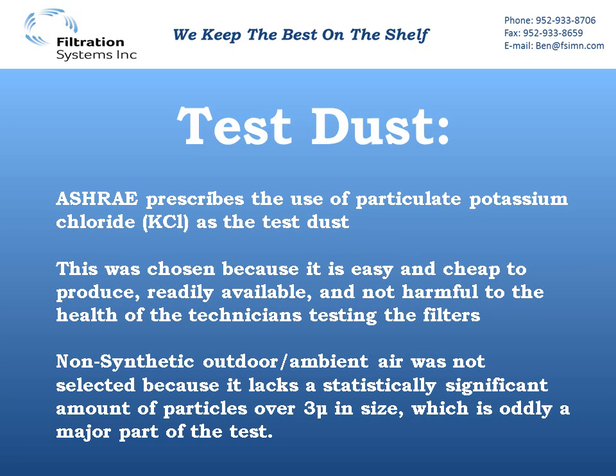Non-synthetic outdoor or ambient air would have been preferable. However, it was passed over because it lacks a statistically significant amount of particles over 3 microns in size, which is a major part of 52.2. So the first limitation to realize is that a major portion of the test is done on a particle size that doesn't naturally occur with any significance in outdoor air.